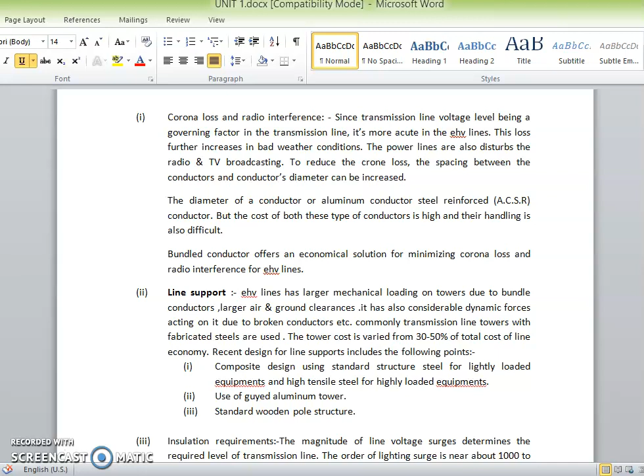Recent designs for line support include the following points: composite design using standard structural steel for lightly loaded equipment and high tensile strength steel for highly loaded equipment, use of guyed aluminum towers, standard wooden pole structures, and insulation requirement. The magnitude of line voltage surge determines the required insulation level of the transmission line.